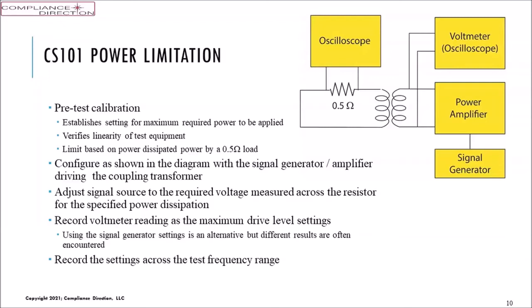A lot of different amplifiers are used throughout the world, so we need to be cautious of that. We've encountered several problems where audio frequency amplifiers are used with a lot of power, but their dynamic range or frequency range gets to be limited. They're good up to 20, 30 kilohertz maybe, and then they start not being very good at the 100 kilohertz region. So our attenuation or operation of the amplifier becomes highly distorted. So we have to be cautious in our calibration to see that throughout the frequency range we maintain a good linear operation of the power amp. Hopefully that answered. All right, thank you.